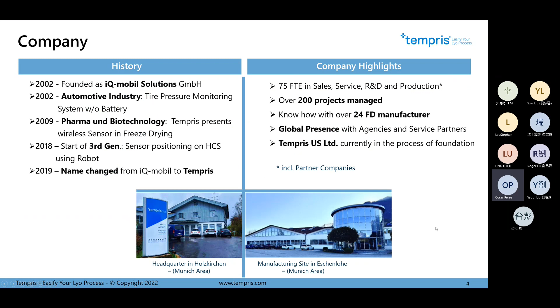Let's talk a little about the technology, because we want to know how it works. Basically, this is a radio frequency technology, and the sensors have no battery, no cable, and no energy source. So how does the sensor work? Basically, we have a main measuring device, which generates the radio frequency signal and gets the data from the sensors. We have interrogation antennas, which send and catch the signal from the sensors. And we have the sensors, which are normally placed in vials, in bulk, and in different applications for measuring the product temperature.